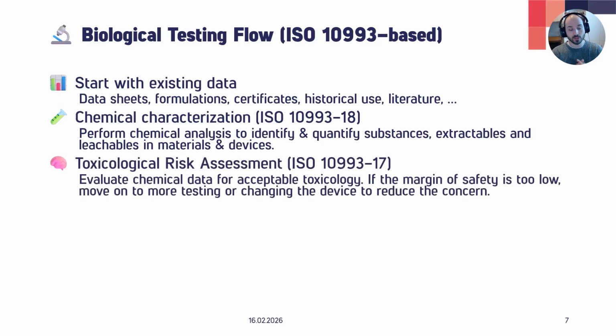And then what we do with this is, okay, this is what could come out of the material. And now we do a toxicological risk assessment, meaning we look at the concentration of each chemical coming out of the material or of the device. And then we make an assessment if this exposure to a patient would be critical or not. So what we do is we make a calculation of the margin of safety.